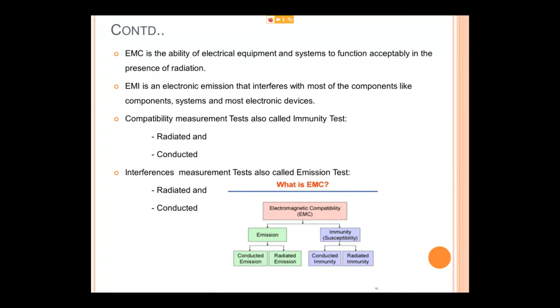The next one is EMI. EMI test is about electronic emission that interferes with other components, systems, or neighboring electronic devices. That's the emission made out of your device. So the first test is whether it can withstand a radiated environment, meaning how long it can withstand it. The second is how much it will emit and cause interference to others.